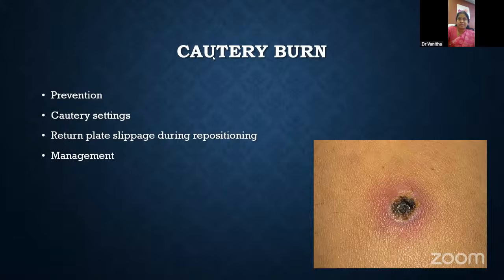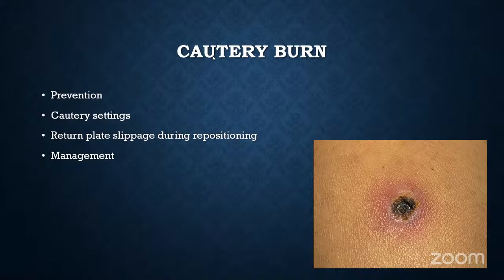First thing, when you start as a freelance surgeon, you have to look at what generator it is, what the settings are to be kept properly, whether the return plate is kept properly grounded, in contact with the patient, and does it have any contact with the metal? All these really need to be done very meticulously for us to avoid these sort of burns. One important thing is sometimes when we have serviced the machine, this particular patient, we had it after we serviced the machine. We thought we increased the current setting a little more, and we were never thinking about this grounding somewhere else. We were thinking that the machine is not working.